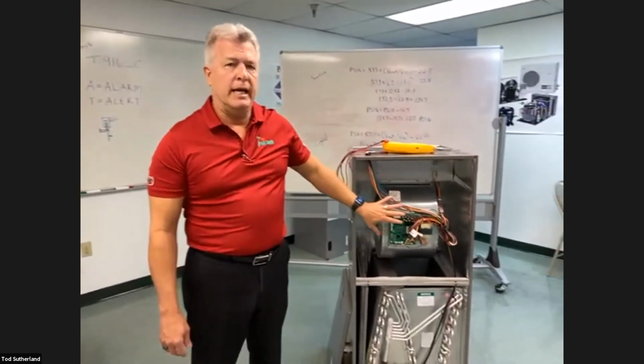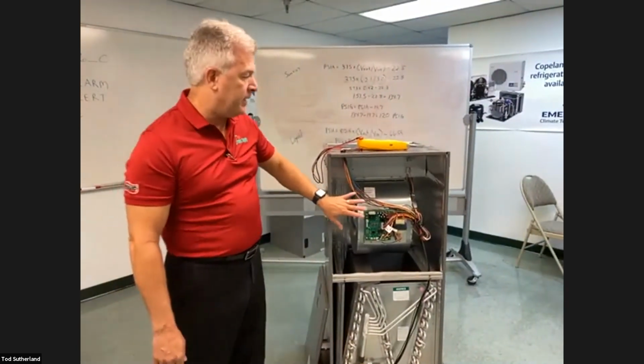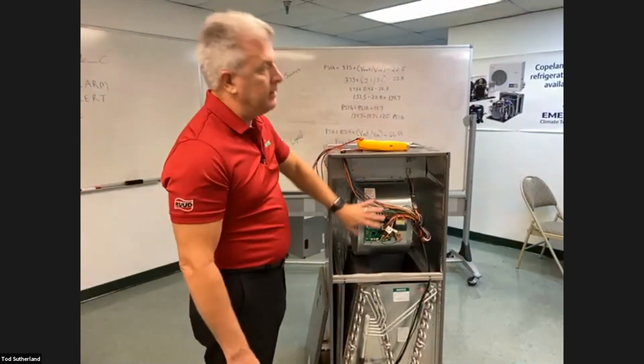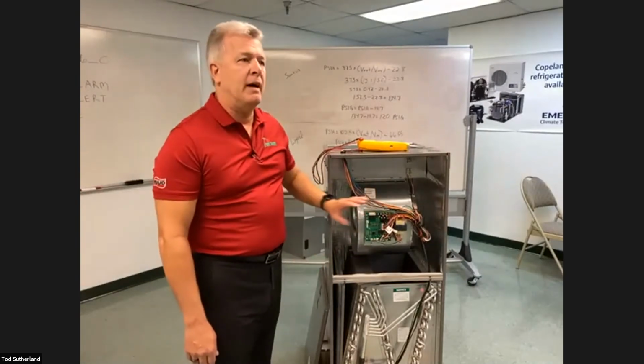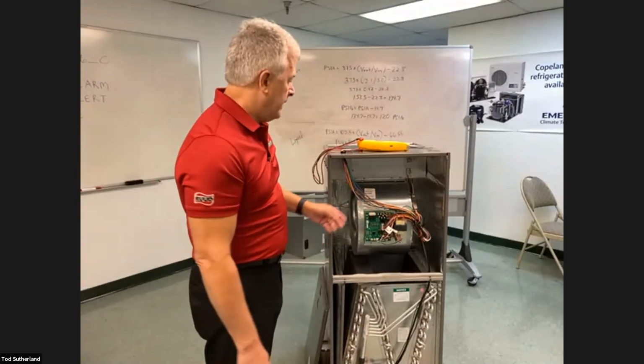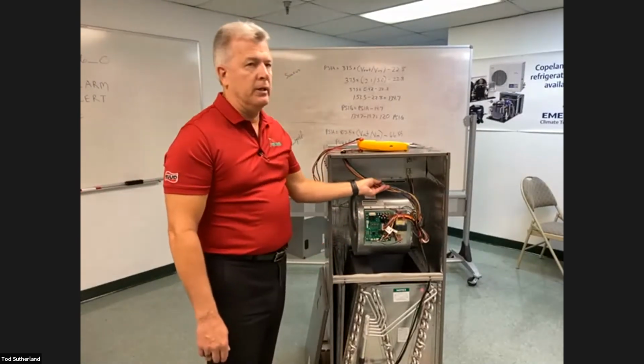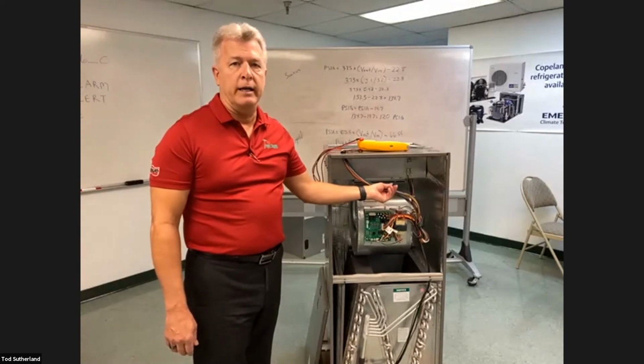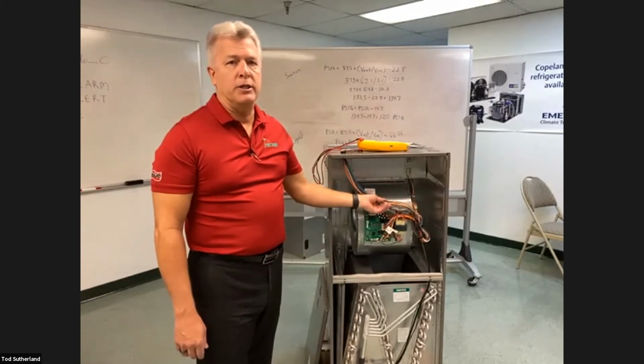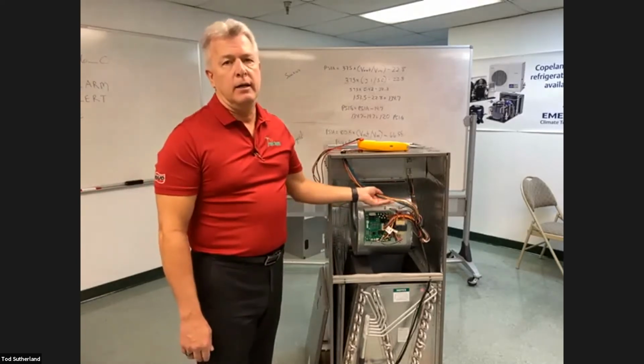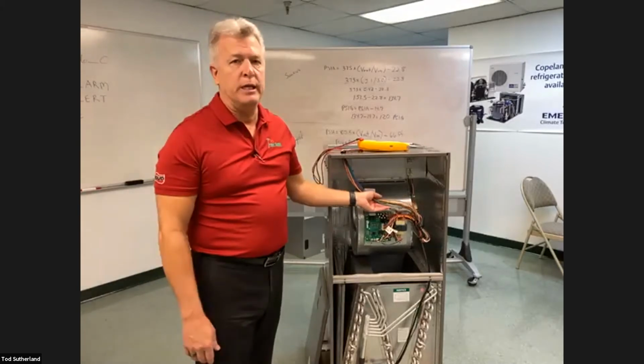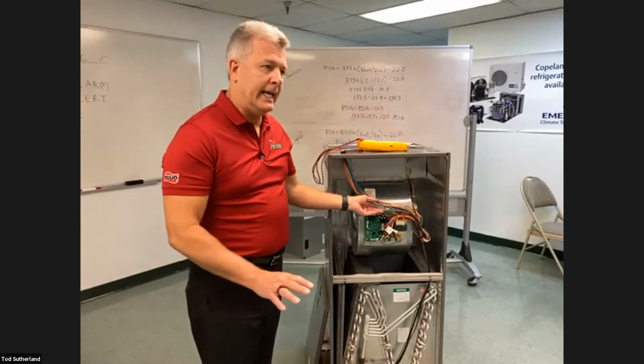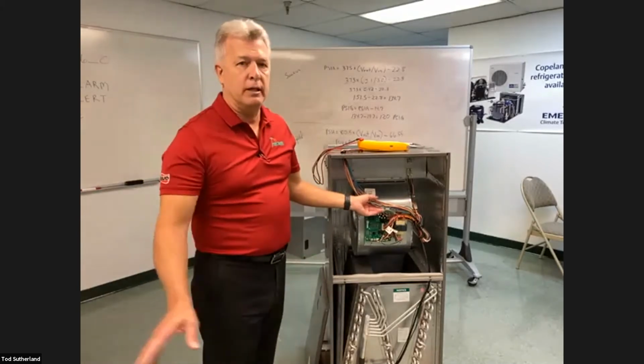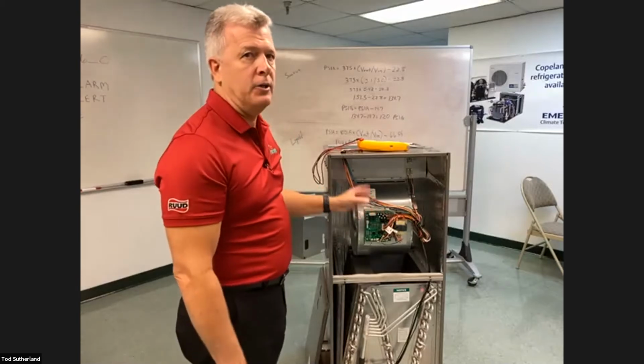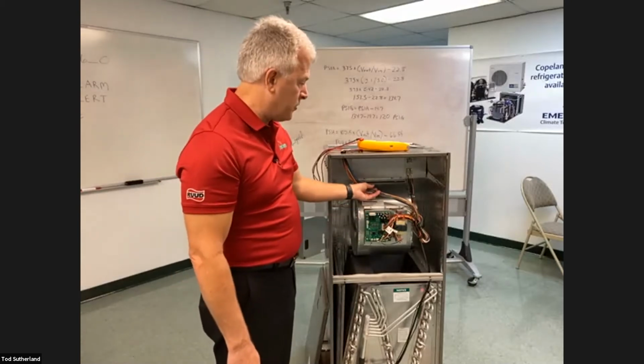Again, looking at the air handler can be intimidating because there's a ton of wires in here. Unfortunately, the only reason we have a ton of wires in here is that we have to have availability to connect this legacy wiring as well. There are 7 wires that you'll need to connect to the thermostat in case you weren't using our EcoNet controller, which again should only be done in an emergency. Other than that, you always want to use the EcoNet controller.